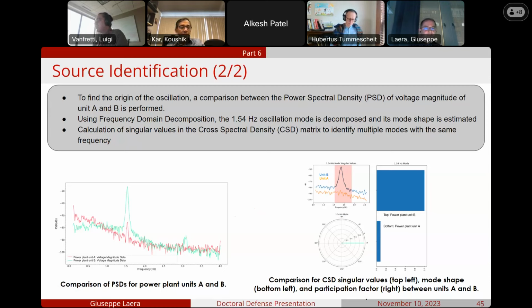And the singular value calculation of both data sets identifies only one mode at 1.54 Hertz, with a higher value for unit B than for unit A. The mode shape calculation also shows a higher value for unit B compared to unit A. And finally, the normalized participation factor, if we consider it equal to 1 for unit B, then the corresponding one for unit A is 0.008. So all these results converge to the fact that unit B is the source of the observed oscillation.